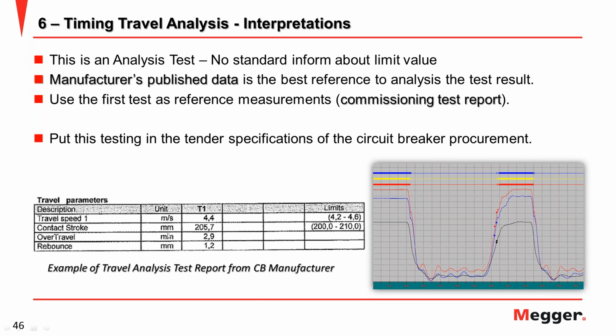This is an example of the report from the commissioning from the OEM breaker. They provide this information: speed, stroke value, over travel, how much the over travel is when the breaker operates, and rebounds, like the vibration on the mechanical part. So you will get this information from the OEM manufacturer, and this is the result example for the open close operation like this.